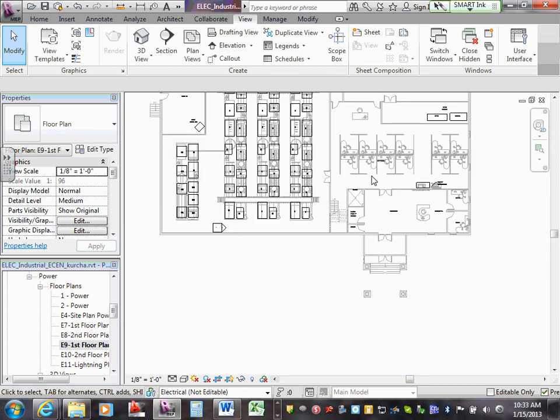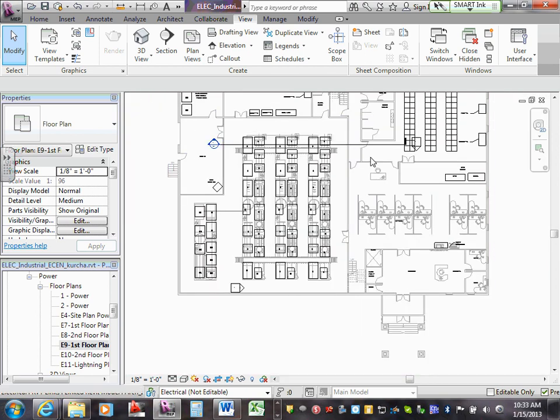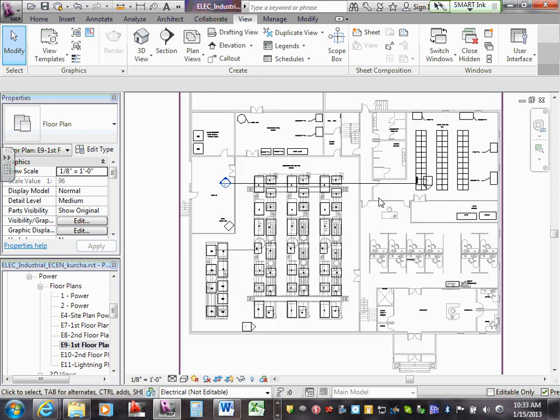But now we're going to talk about the clean room office. Actually, get into notification real quick. For an occupancy fully sprinkled, the code says you do not have to have any notification in the building. However, the owner may come back to you and say our insurance company is requiring us to put notification throughout the entire facility. That's where a lot of this will come in.